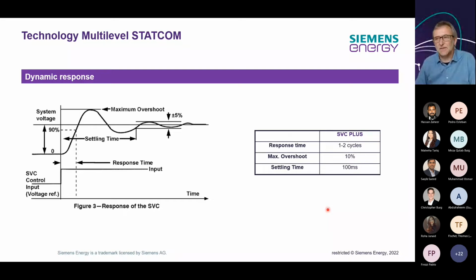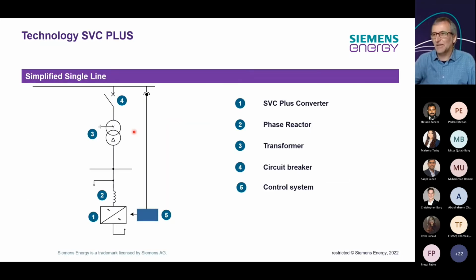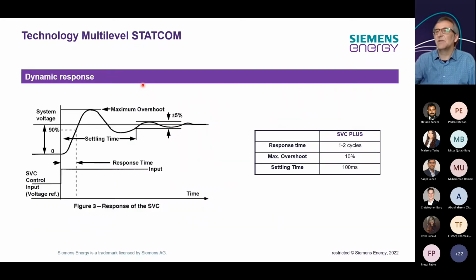For the performance of the system, it is quite important to understand a bit the way the control works. And as we said, let me go back, we control on the high voltage grid. If the voltage of the grid would, for example, have a drop, it will be detected. And then you would apply a voltage to the converter and feed in to bring up the voltage to where it was. But this will depend very much on the strength of the system. So if you have a very strong system, you need more power. Compared to a weak system, to a weak grid, you need less power.